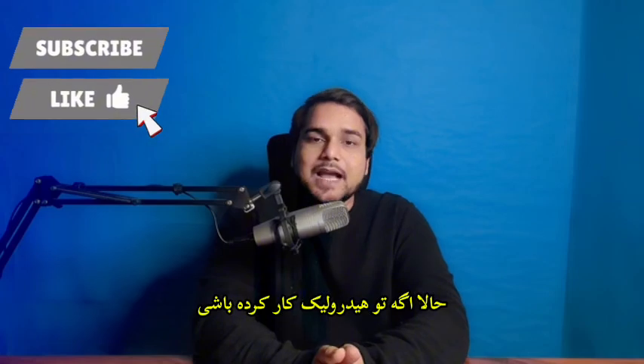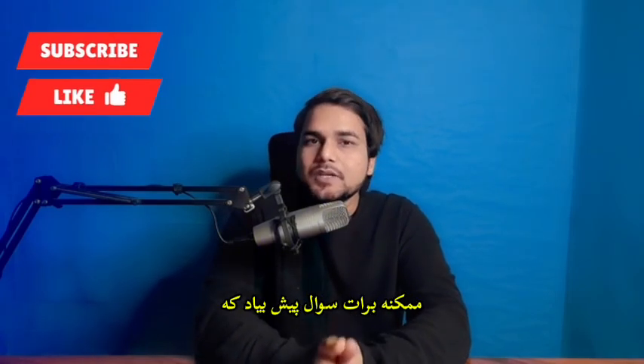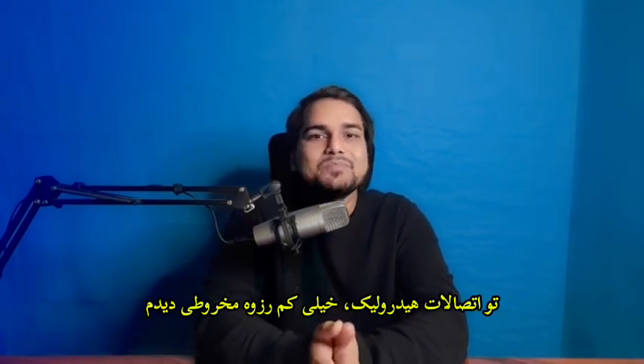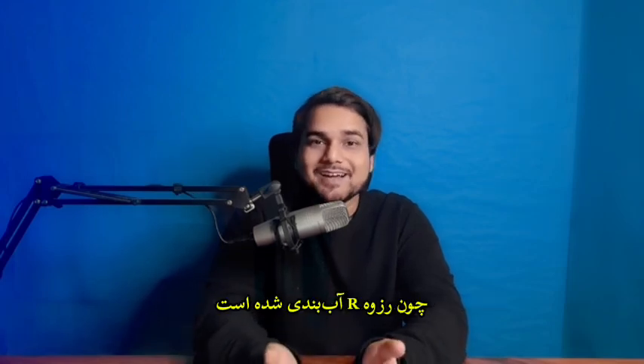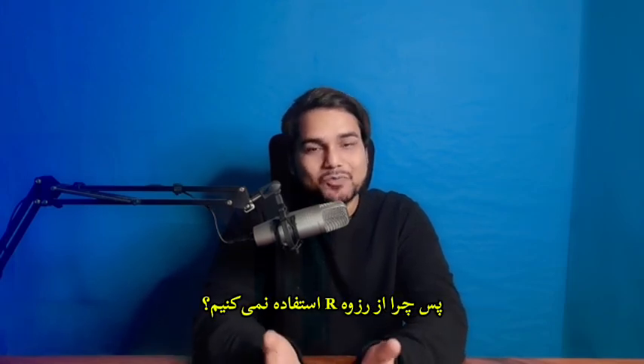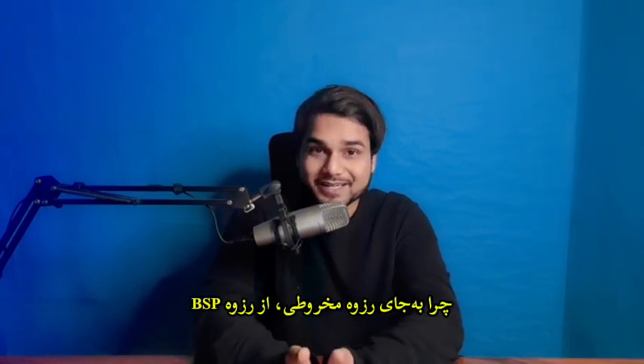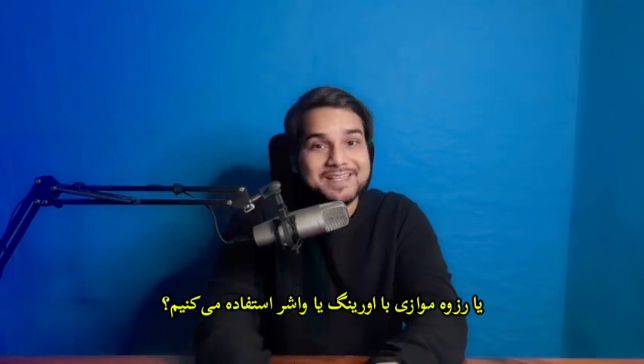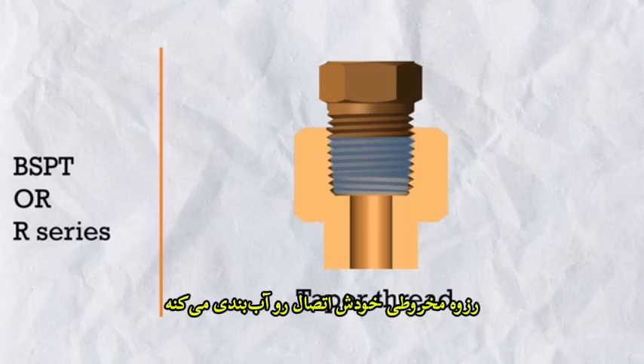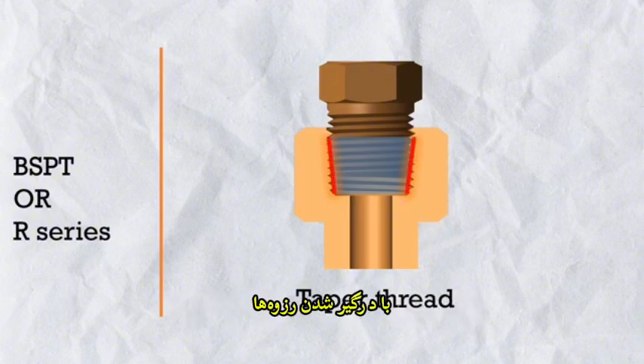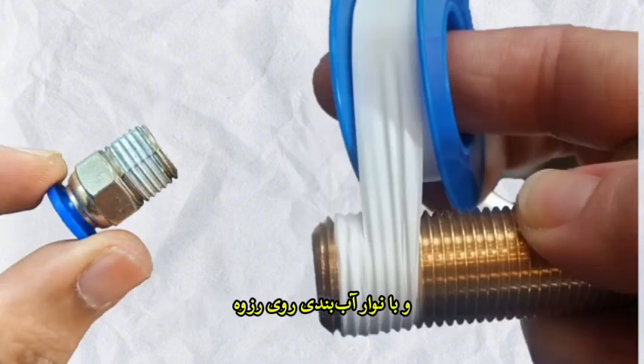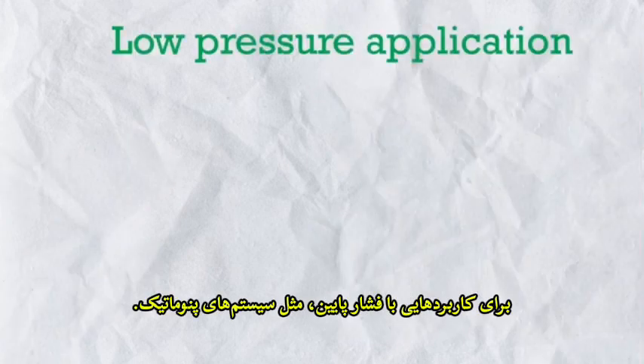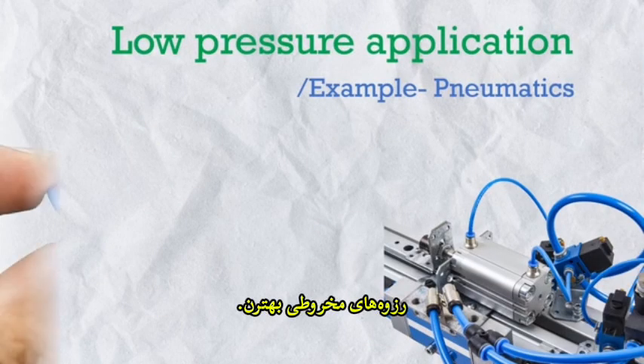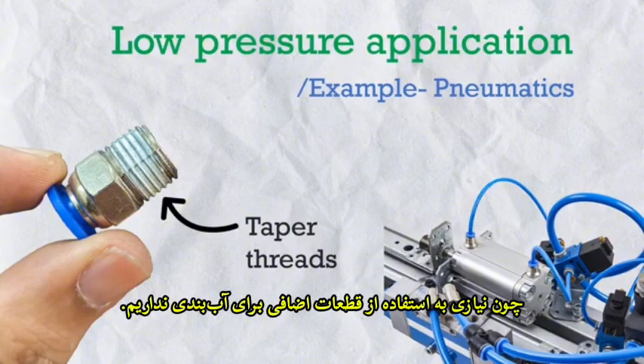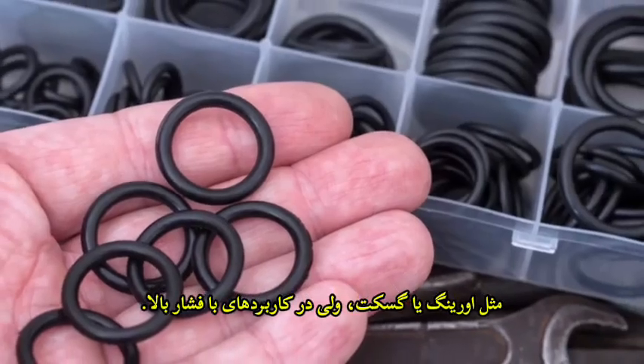Now, if you have worked in hydraulics, you may be wondering, Ayush, I have rarely seen any taper thread in hydraulic fittings. So as R thread is a sealed thread, why do we not use R thread? Taper thread, why do we use BSP thread, parallel thread with O-ring or gasket? So here is the thing. The taper thread seals the connection with thread interlocking and the sealing tape over the thread. Because of that, for low pressure applications like in pneumatics, taper threads are better because we don't need to use extra sealing elements like O-ring or gasket.